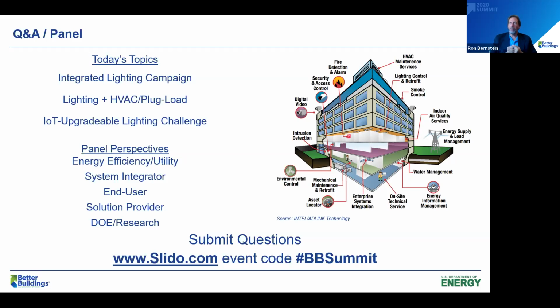And the third one, which ties in and we've already mentioned, is energy monitoring through real-time metering. We've talked about that from the standpoint of capturing data to report back over time, but I think there's also an advantage to looking at energy monitoring on a real-time basis for things like out-of-range or maintenance alerts, where a piece of equipment has failed and is using energy when it shouldn't - that happens a lot on HVAC equipment, but it could happen on other systems too. So those are three things we've mentioned, but there are advanced capabilities there that could lead to benefits on the consumption side, the energy side, and the occupant comfort side. I'll leave it at that.